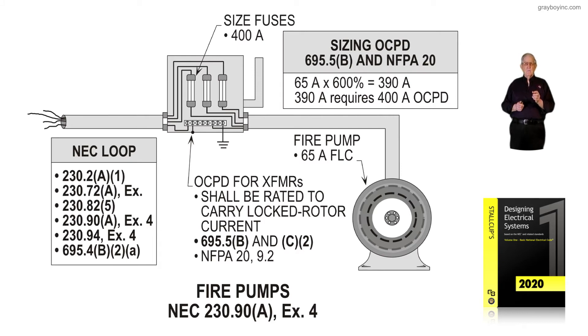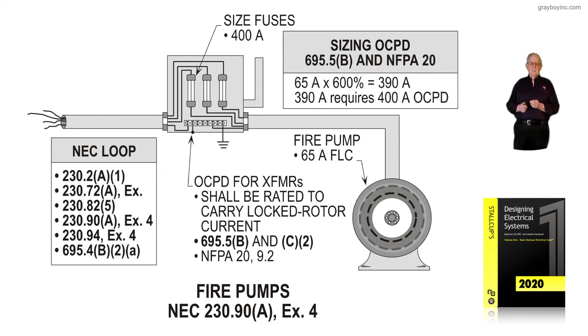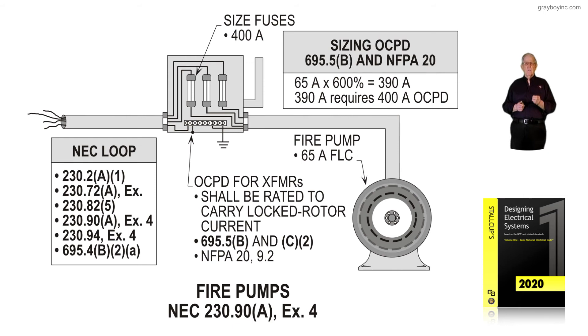It is highly suggested that you review the NEC loop sections. 230.2A1 allows another service in addition to the normal service for a fire pump. 230.72A exception says you don't have to group it either. And in 230.82, item 5 says you can tap ahead of a main that is considered reliable service if the authority having jurisdiction gives you permission to do so.